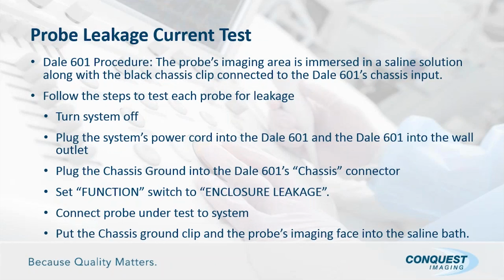You have to test each probe. It's an important concept. You will go into a room and they'll have 2 probes plugged in, and they'll have 5 hanging on the wall. Well, you have to test all 7 of those probes from an electrical safety and imaging perspective. So make sure that you're checking with your customer while you're doing this electrical safety on an ultrasound system to verify the safety of all probes that they have access to.